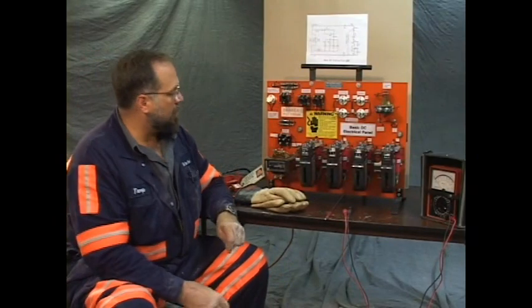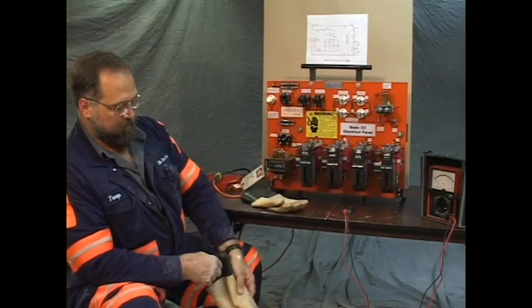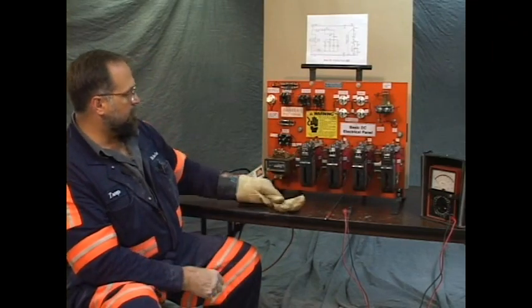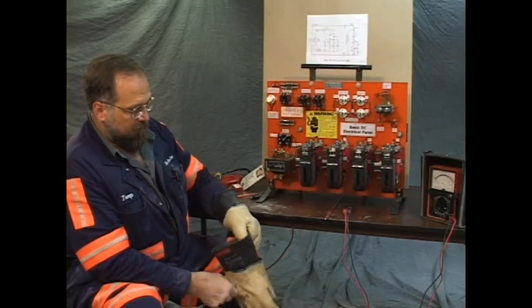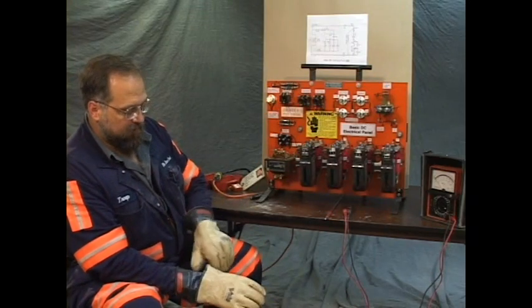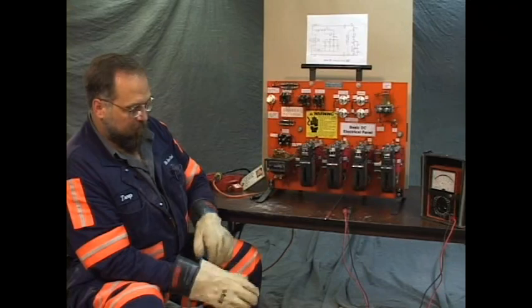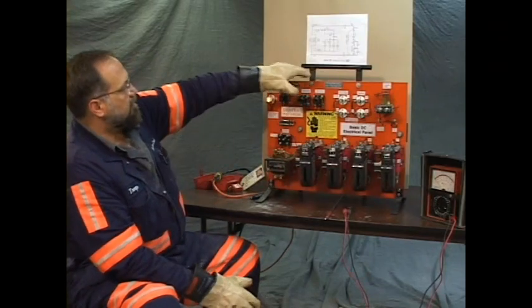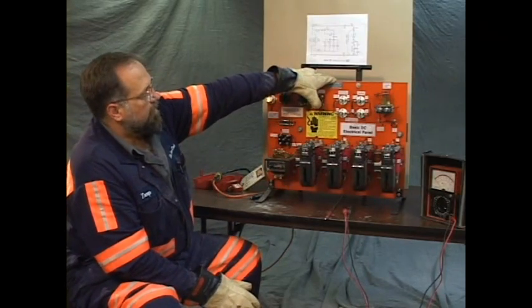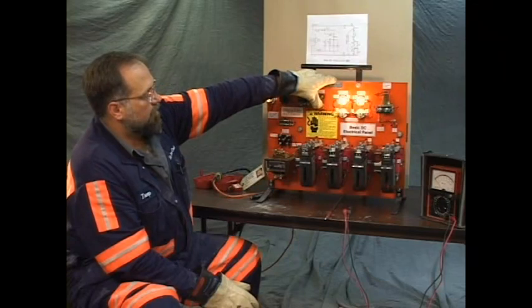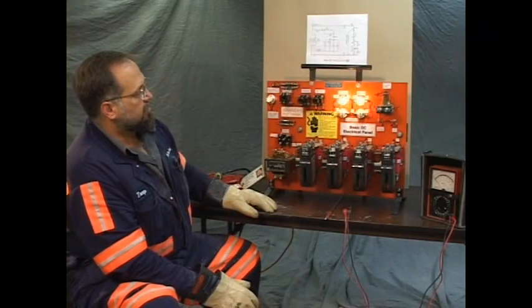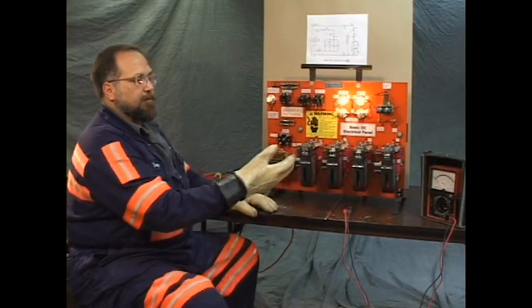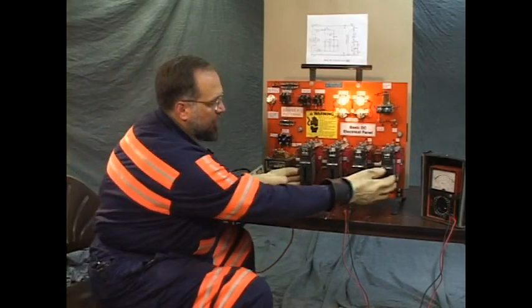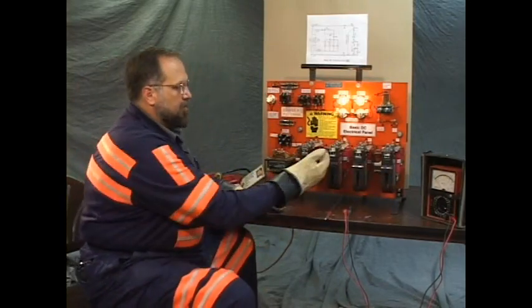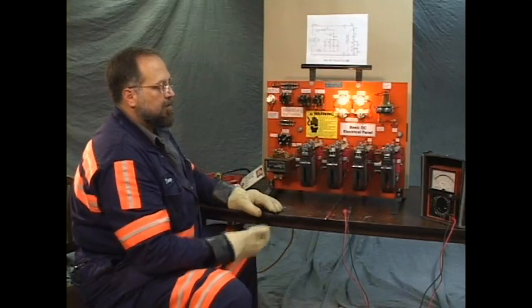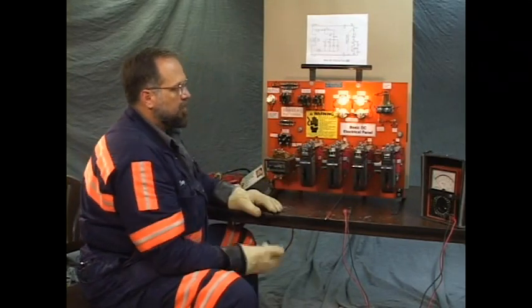We're going to show a normal operation of the panel first. We'll put our gloves on. A lot of these components on this trainer here are energized whenever the panel has power on it. Here we go. For normal operation, you press the start switch, you hear 3 clicks. M1 and M2 go in simultaneously. After 1 second, 1A goes in. After another second, 2A goes in.